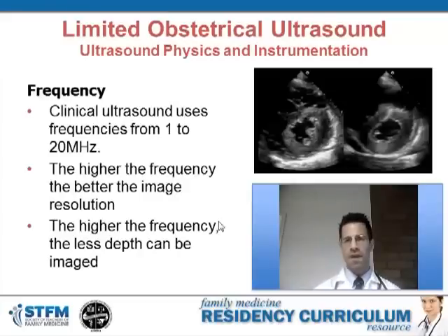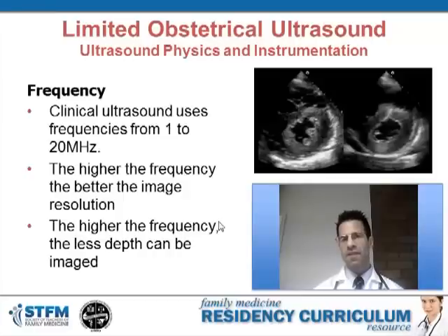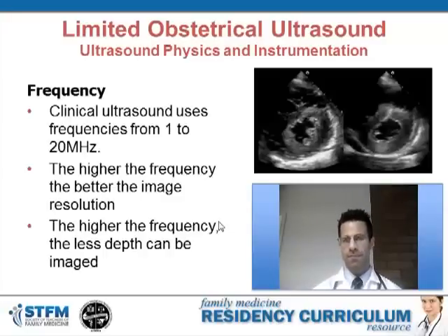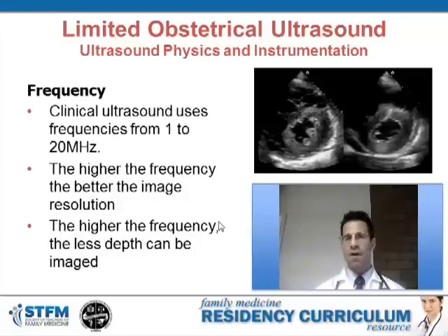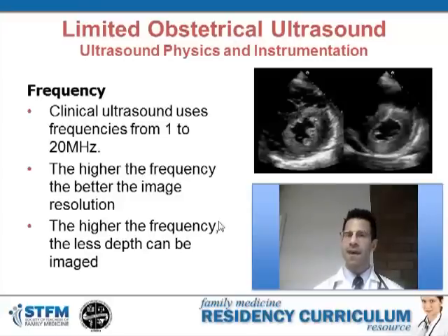Clinical ultrasound uses a variety of frequencies to create images. The range is typically between 1 and 20 megahertz, with the most common range being between 2 and 10 megahertz. The higher the frequency of the probe, the greater the resolution of the image created. However, the trade-off is that higher frequency probes have less depth penetration into the tissue.